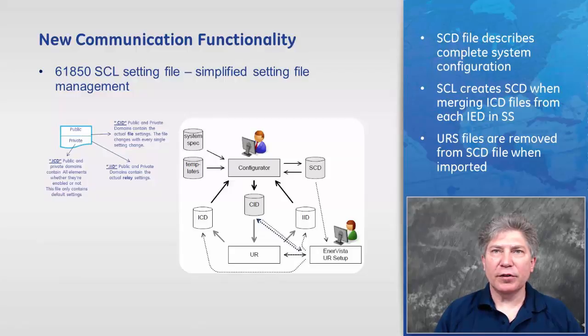Typically, a System Configurator tool creates an SCD file by merging an ICD file from each IED in the substation, then configuring or mapping of the Goose message and report control blocks. EnerVista UR Setup accepts the SCD file, saves the settings for any UR relays as a URS file. EnerVista UR Setup can then send the settings in these URS files to the corresponding UR devices.